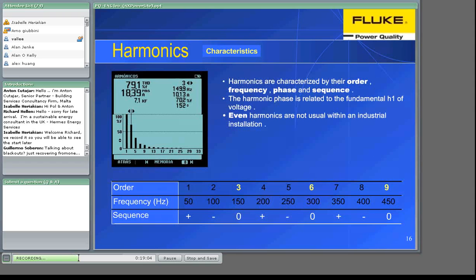Harmonics are characterized by order, frequency, phase, and sequence. By the order, we have odd and even harmonics. Even harmonics are nowadays rare. They are generated by an unsymmetrical waveform where the positive and the negative half cycles have different shape and magnitude. They were common when half-wave rectification was widely used. For instance, long time ago, black and white television used a simple diode cutting up the sine wave, producing the second harmonic. In a clean network, we have a positive sequence only.